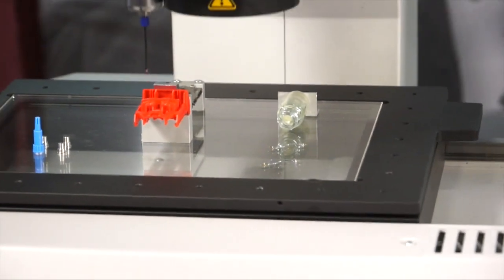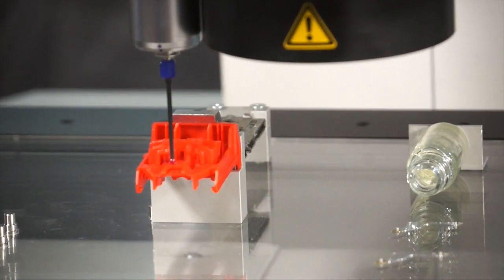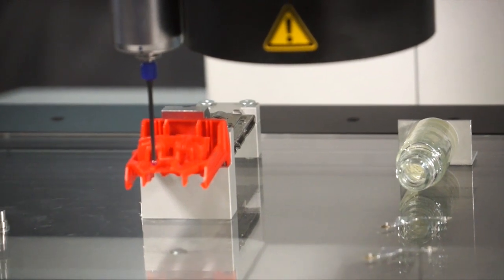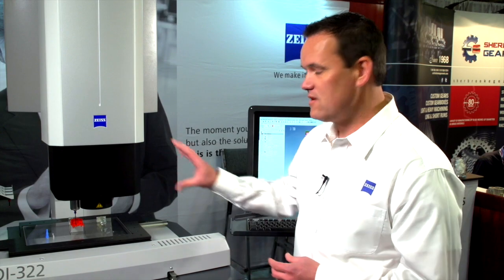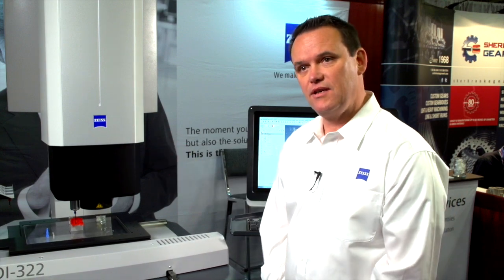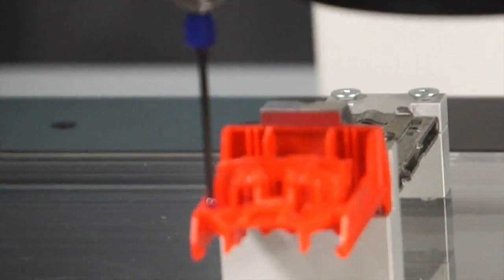Being a multi-sensor system, we have the tactile scanning probe off to the left there. As you can see, this step is measuring the profile of that plane. The tactile scanning along with the optics enables you to measure quite a few different geometries.